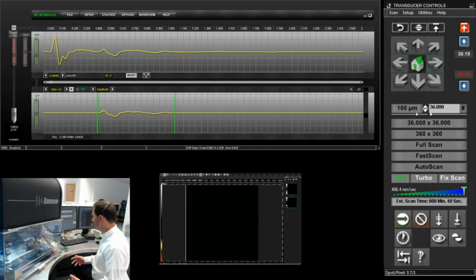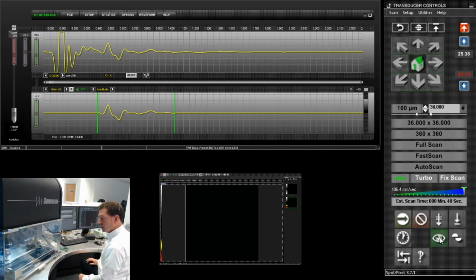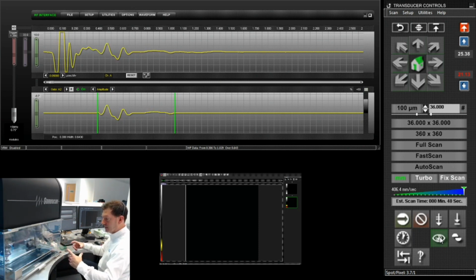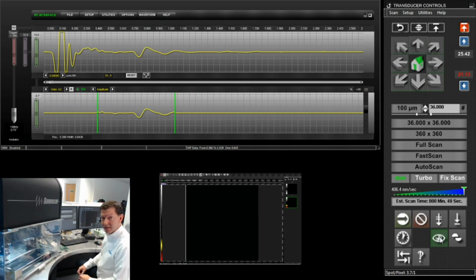If you're used to the system, it's quite easy, but if you prefer to use the automatic method, we can do that as well. So back to the transducer control window, we have an icon that looks like an eyeball. So if we click this, you do have to be over the part first before you click this and have a valid signal, which we do, so we can go ahead and click that. And in this case, the transducer will move to each of the sides and calculate the scan size and the center of the device at the same time.